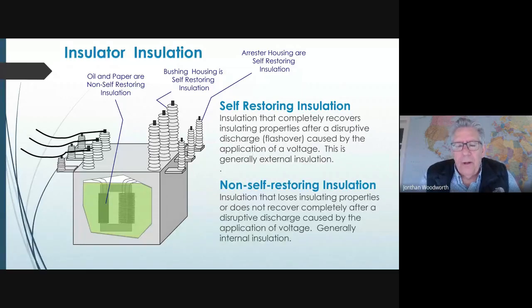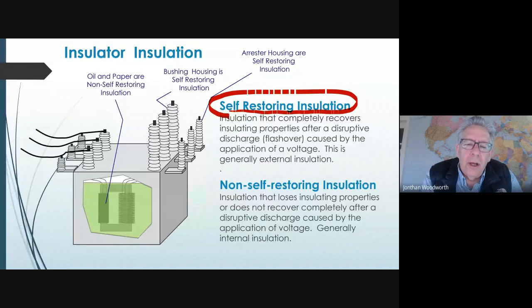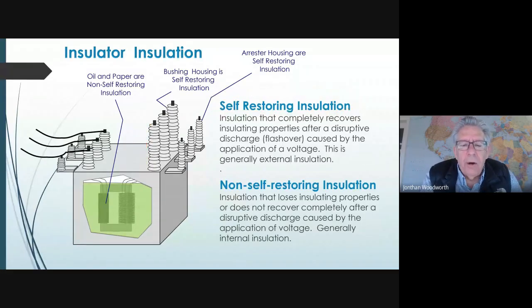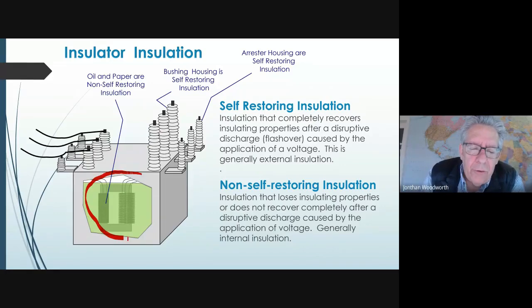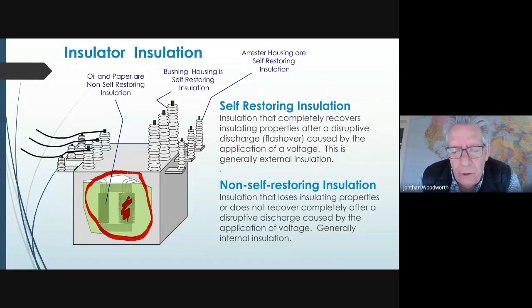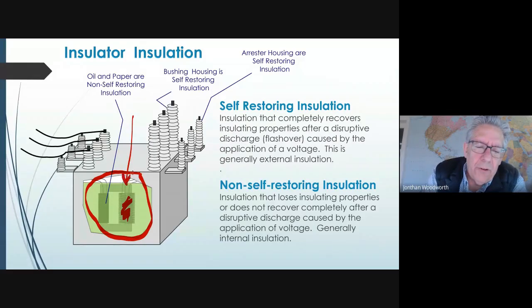Before we get to those animated slides, though, just a few definitions. We have two kinds of insulation. One is called self-restoring insulation, and that's usually an insulator that if it flashes over, then after the flashover and after a breaker operates, it'll self-restore and go back into service by itself. That's self-restoring insulation, and most of the insulation in a power system is that way. However, the non-self-restoring insulation, where if it fails on the inside, it's over. It's done. There's no restoring it. It needs to be fixed, taken down out of the system and fixed. So that's why we focus on this insulation, because we never want to have to get in there and fix the power system on the inside.